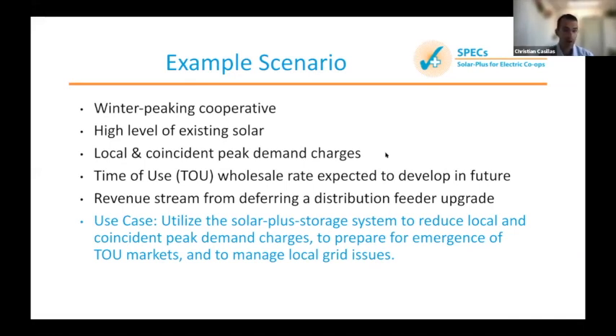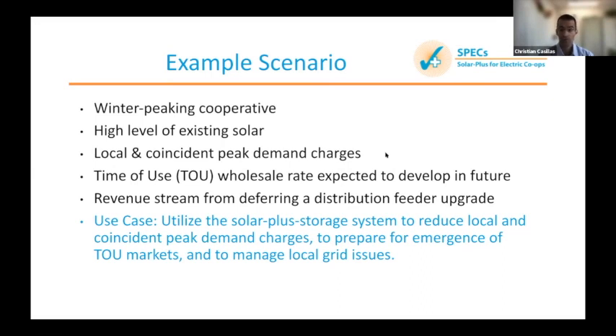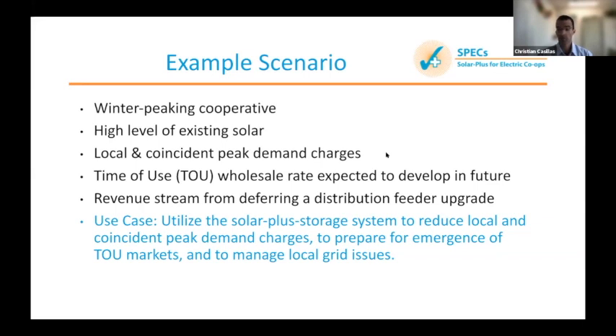We're also going to explore the potential for a time-of-use wholesale rate that may be in the works in the future — there are tools within the SPECS model to explore the benefits of that. Additionally, they already have solar on their system in some places, and they've got a distribution feeder experiencing high congestion that will need an upgrade. That feeder upgrade can be deferred due to the implementation of battery energy storage on it, creating a resulting revenue stream. We'll analyze the costs and benefits of reducing local and coincident peak demand charges, preparing for the emergence of time-of-use markets, and infrastructure deferral through integration of a solar and battery system.